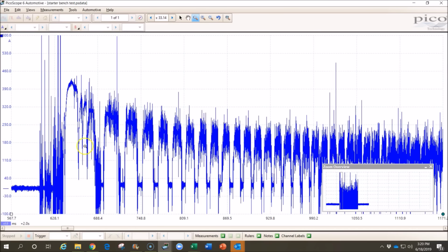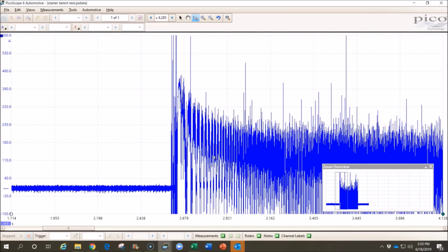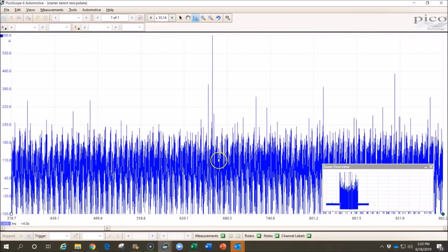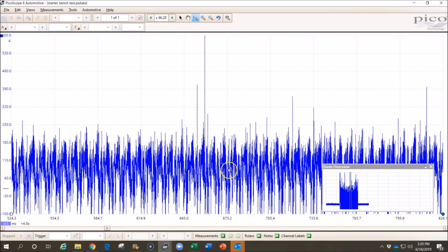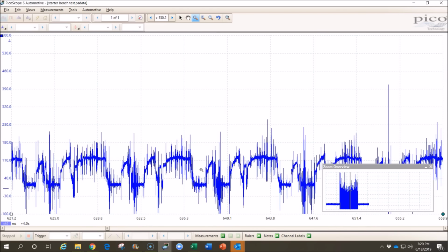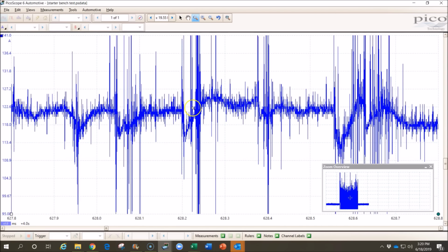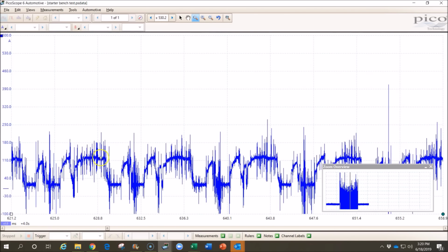Now as we look at this one, when we zoom out, you can almost see the pattern here that we wanted to see. But if you zoom in closer, you'll see that it drops all the way down to 0. So some of the brushes are making contact, but what we should see, we should see this hash without all of these dropouts. During every revolution of the starter motor, it actually loses contact completely on some of the commutator segments, and it drops out to 0 amps.